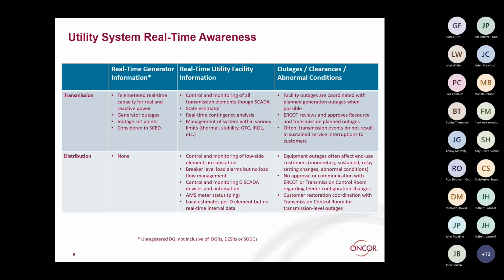When it comes to measuring points and operational set points for relays, your fault current constantly changes as you're reconfiguring your distribution facilities. You may have a totally different situation one week versus the next based on what activity is going on. I'll point that out later in terms of the amount and number of activities we experience on our distribution system.